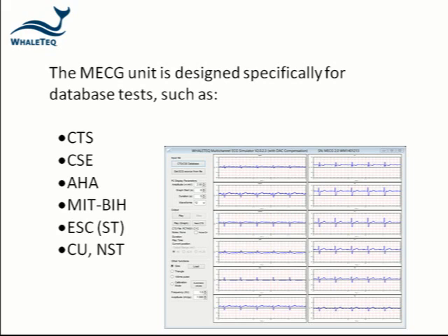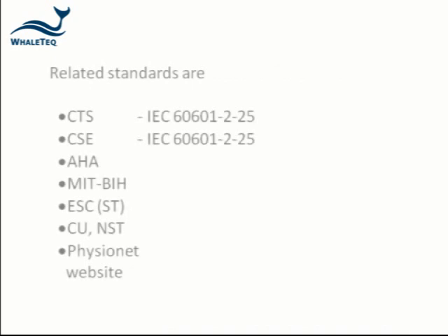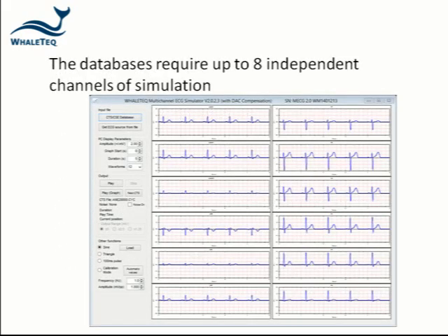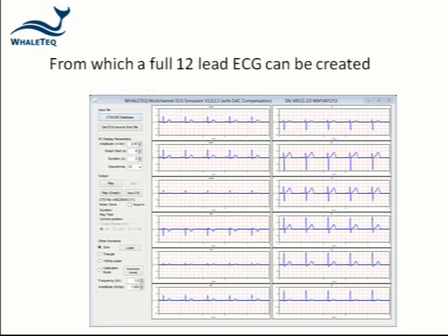These databases are also available from the PhysioNet website, and can be found in standards such as IEC 60601-2-25, 2-47, and AAMI EC57. The databases require up to eight independent channels of simulation, hence the name multi-channel. These eight channels allow a full 12-lead ECG recording to be created.